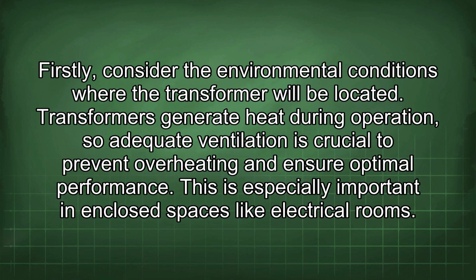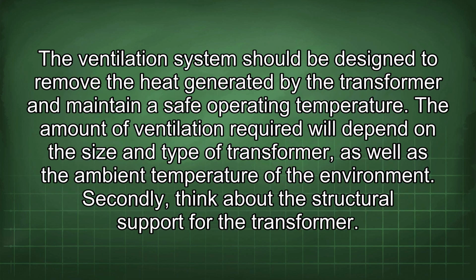Firstly, consider the environmental conditions where the transformer will be located. Transformers generate heat during operation, so adequate ventilation is crucial to prevent overheating and ensure optimal performance. This is especially important in enclosed spaces like electrical rooms. The ventilation system should be designed to remove the heat generated by the transformer and maintain a safe operating temperature.